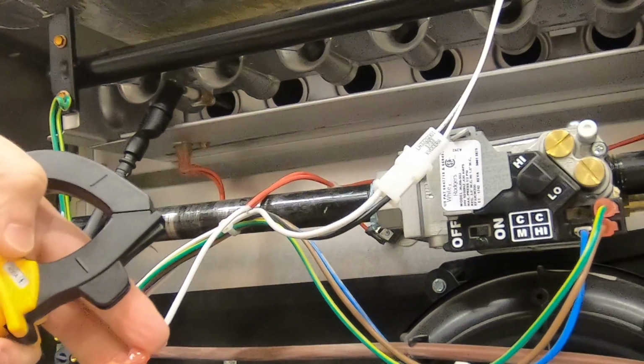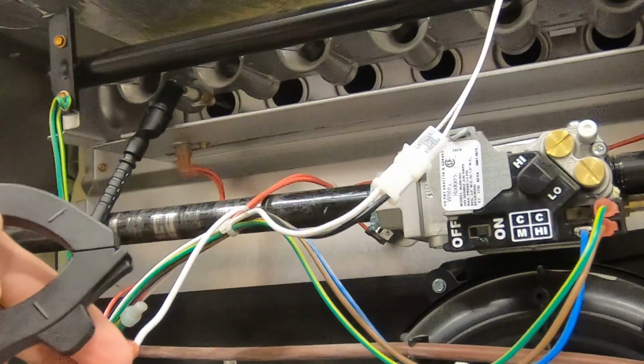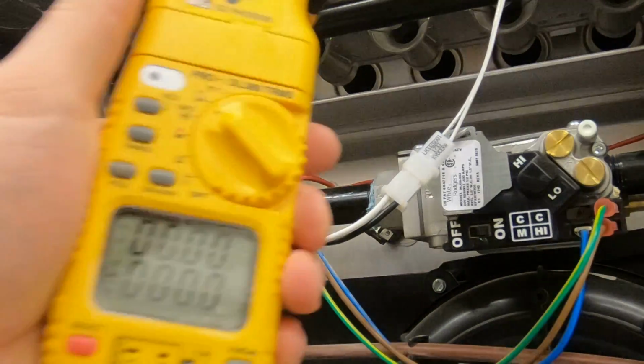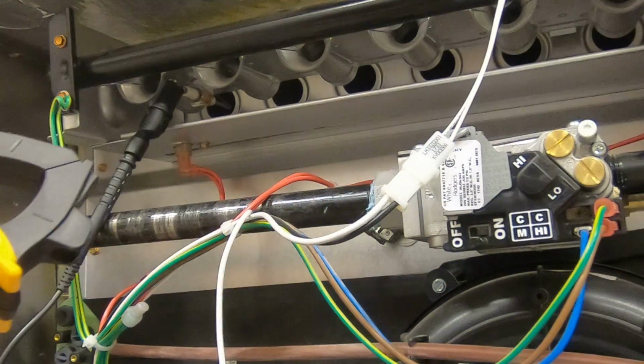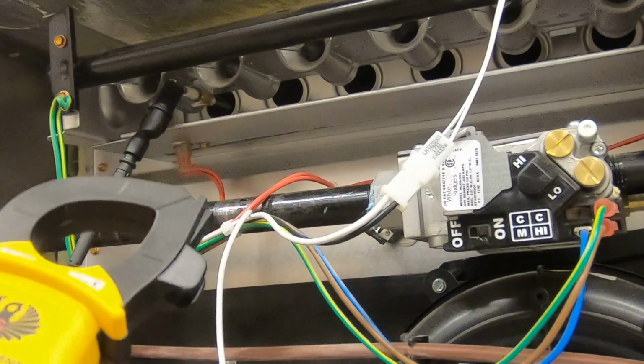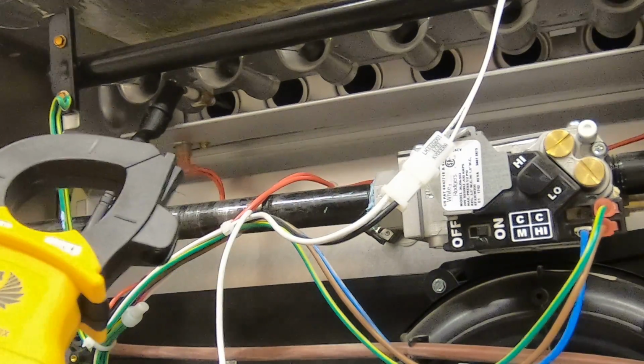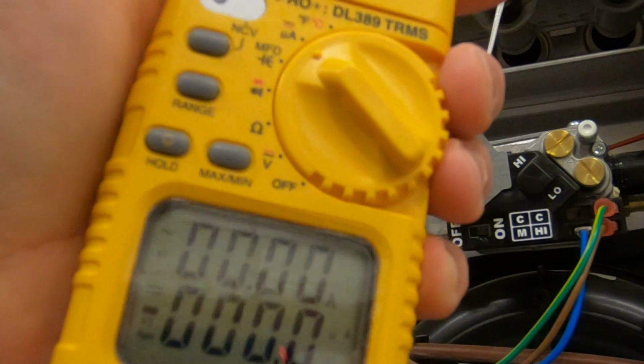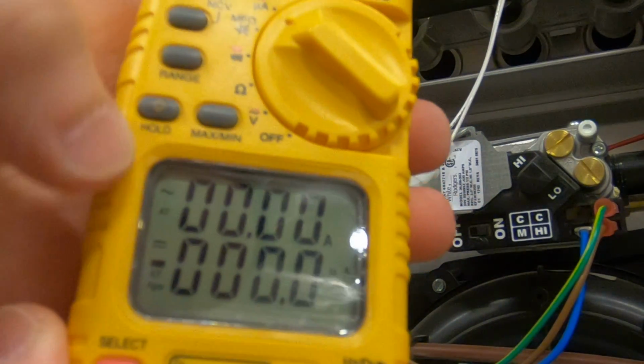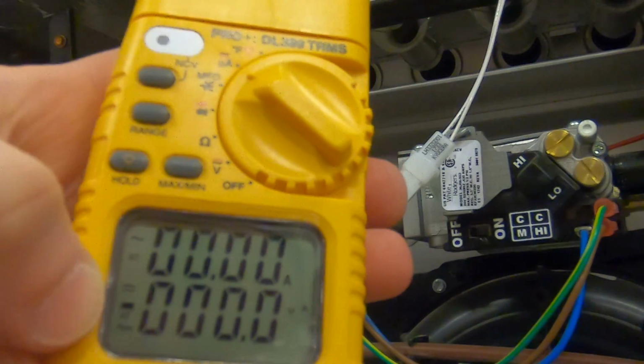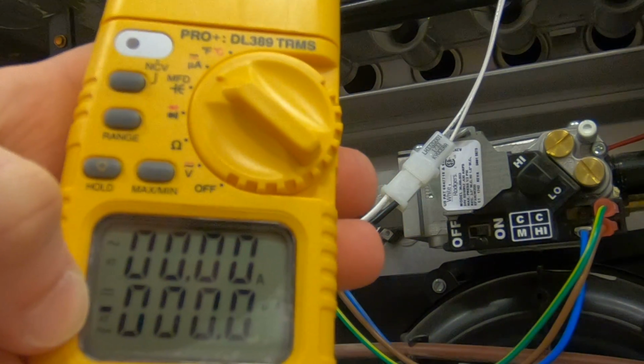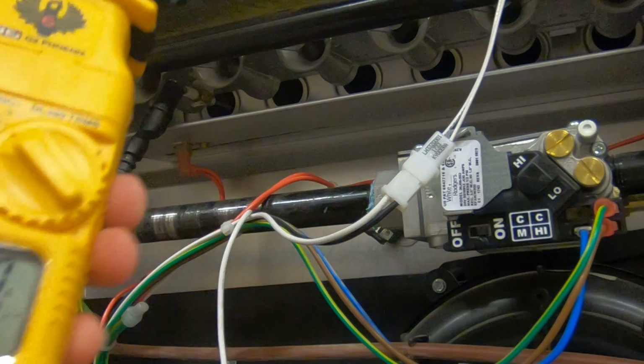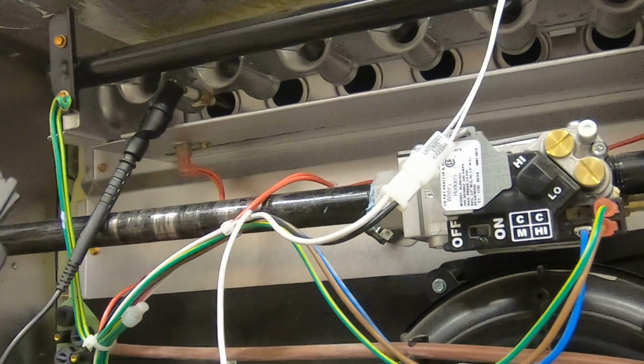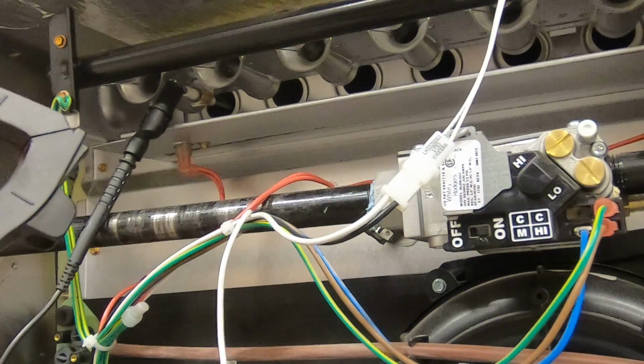And if we hook this one back up in place, we'll watch this number when the machine cycles back through, you'll see it check for UA on this meter. Again, this meter has two numbers. Top number's always reading amperage, bottom number's reading microamps. It will take a minute for the machine to go through its cycles and turn back on.